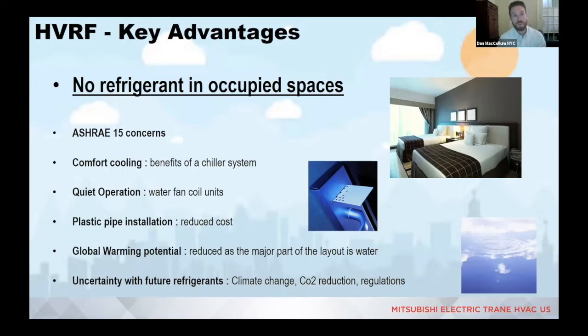What that also will do is allow us to utilize larger VRF systems than we have been able to in the past. Typically, the limit for a VRF system size is a function of the smallest connected indoor space, not the actual capability of the equipment. But now, since we're not piping so much refrigerant to an occupied space, the utilization of larger VRF systems is going to be more achievable. If you're familiar with VRF, you're familiar with the quietness of these systems, and these water fan coil units are, believe it or not, a little bit quieter even.